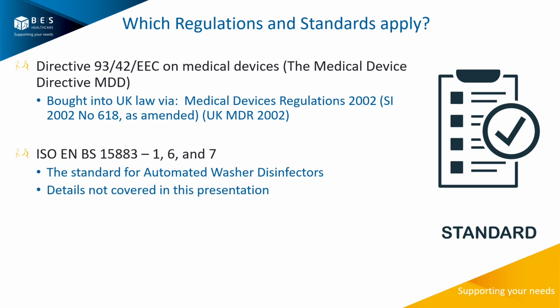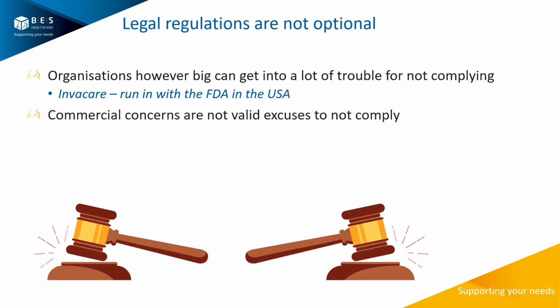Just worth a mention here, I'm not covering it further in the presentation, but there is a standard for automated washer disinfectors. This is ISO 15883. There are a number of parts to it. The only parts that you need to be concerned about are parts 1, 6 and 7. So if you're looking at washer disinfectors in loan stores, you need to be aware of that standard and products needing to comply with it as well. But I'm not covering that any further in this presentation. I'm focusing on the Medical Device Directive.